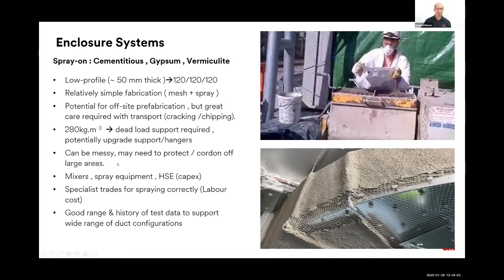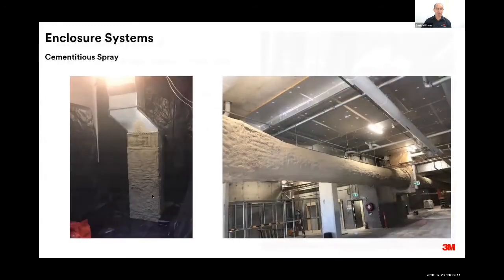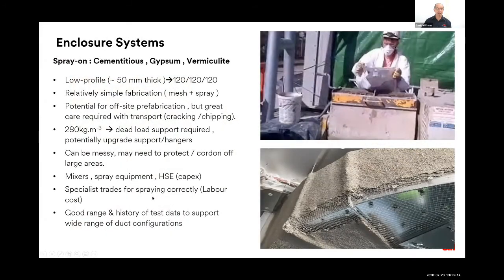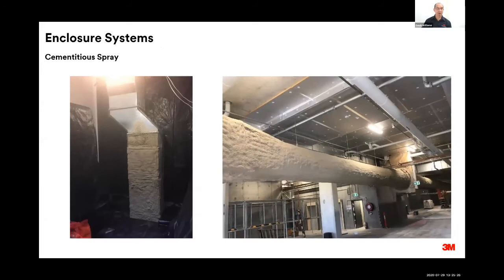With any kind of spray material, it can be messy, so you need to protect the area and cordon off large areas to avoid spray and overspray. There is some capital involved, the equipment such as mixers and spray equipment, and you generally need specialist trades to spray correctly and get the right thickness. But again, with sprays, there's a pretty long history of good test data to support a wide range of configurations. Here's a couple of pictures showing some finished or partly finished spraying of ductwork.